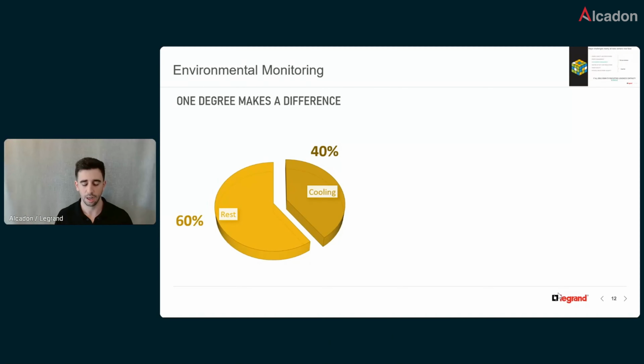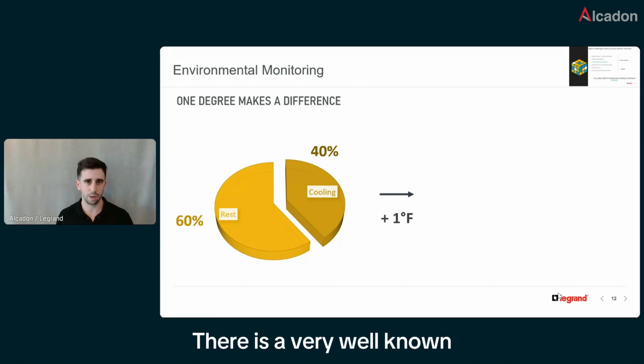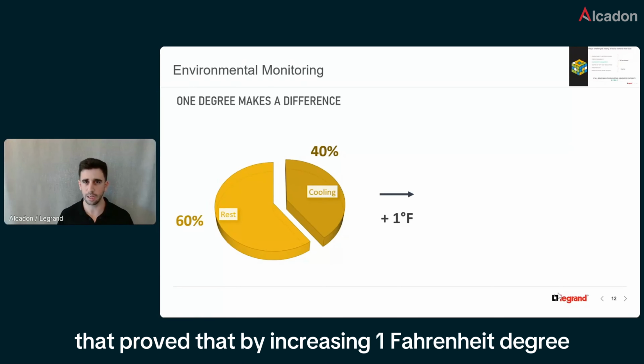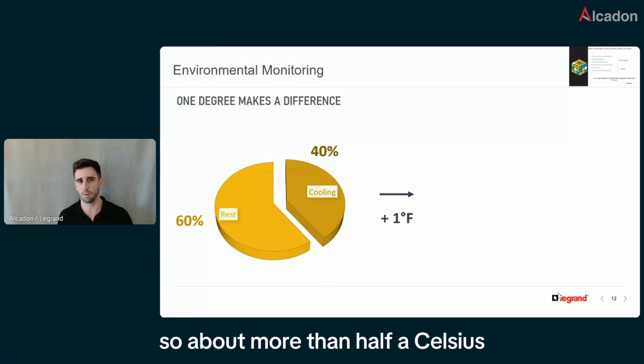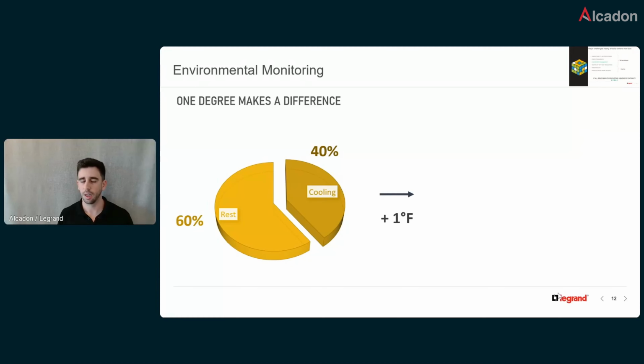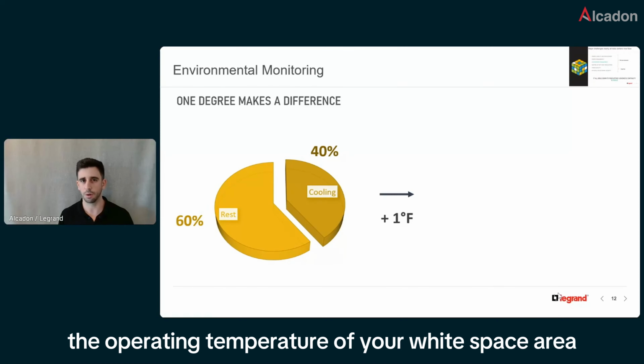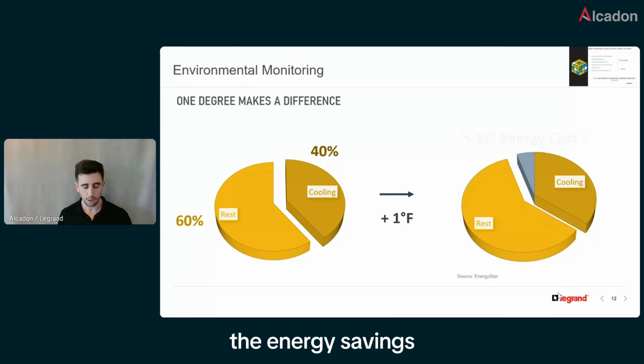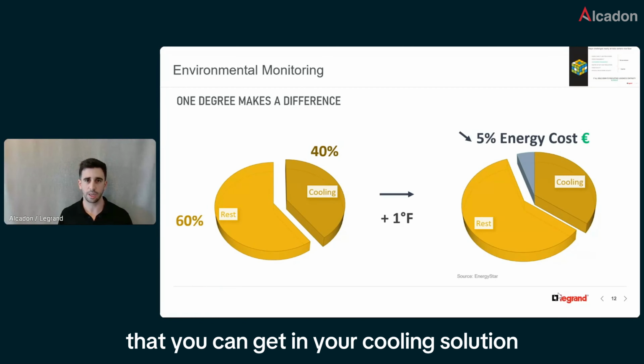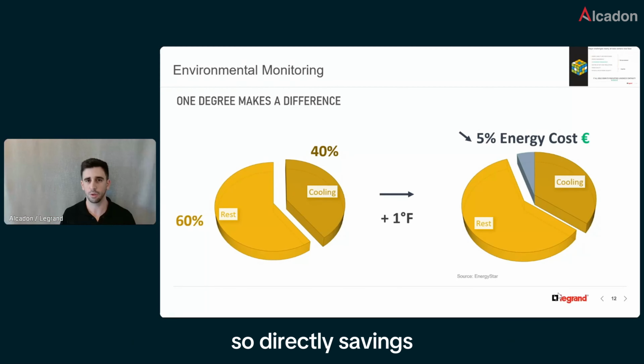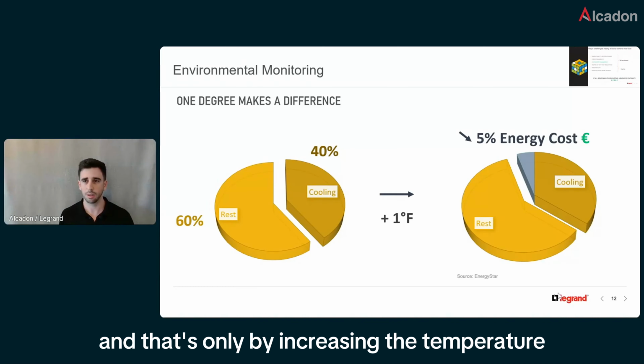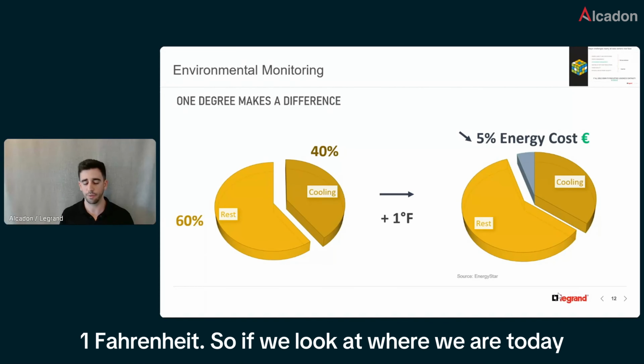That's what I've used here. There's a well-known study from Energy Star that proved that by increasing the operating temperature of your white space area by 1 Fahrenheit degree - about half a Celsius degree - the energy savings you can get in your cooling solution, meaning direct savings on your bill, are about 5%. And that's just from increasing the temperature by 1 Fahrenheit.